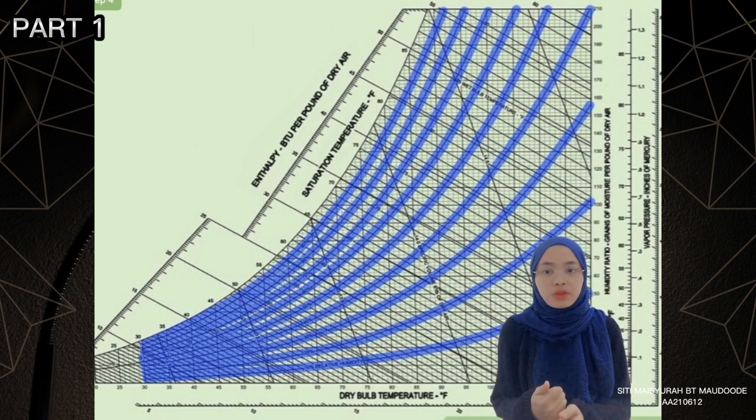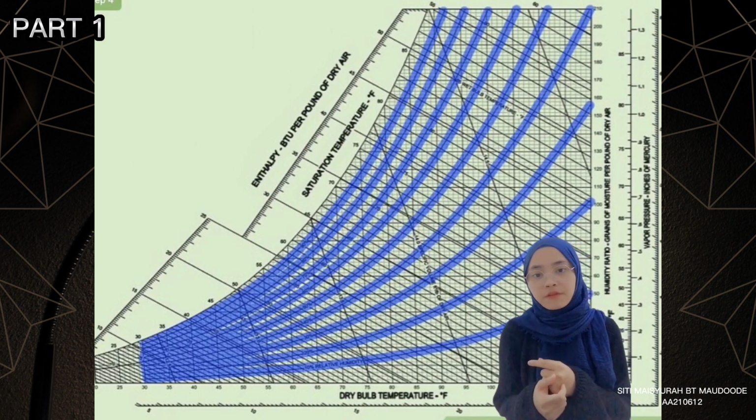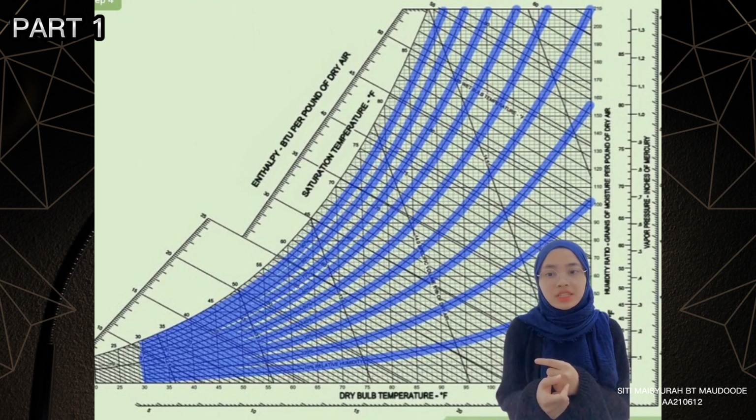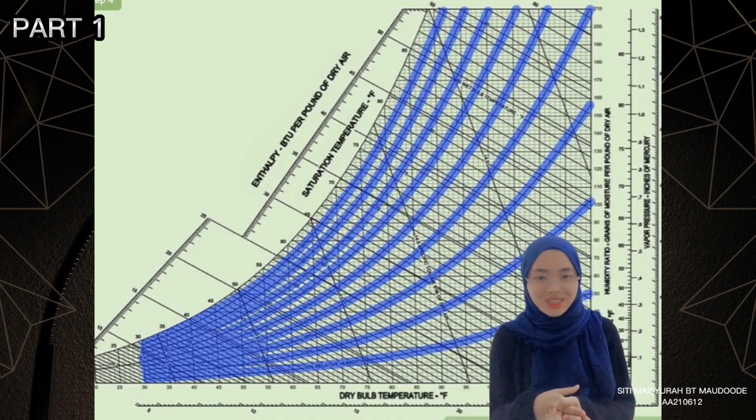Next, we need to follow the interior curved lines to see various levels of relative humidity. On the chart, you will notice various lines that follow the curve of the saturation curve. This marks the relationship between temperature and pressure when the humidity is less than 100%. In most cases, each line away from the saturation curve represents a 10% decrease in saturation.